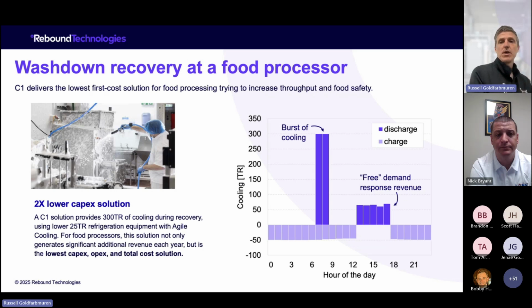And then one more example on the food processing side of things, we have a washdown recovery example. Here in food processing, you have to spray down the facility once a day to sterilize everything. That creates a really hot, humid environment that you have to recover from. During that time, that's perhaps a 4-hour window, your entire facility is idling. So it's a huge waste of your assets, but you can't oversize a chiller to only run 2 hours a day. The economics just don't work out.